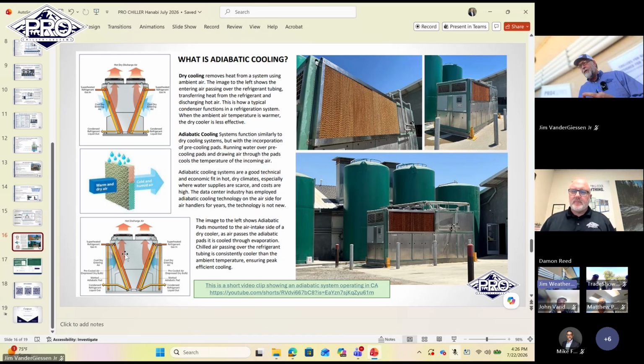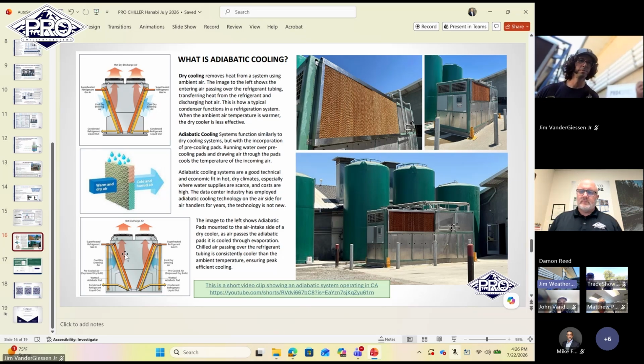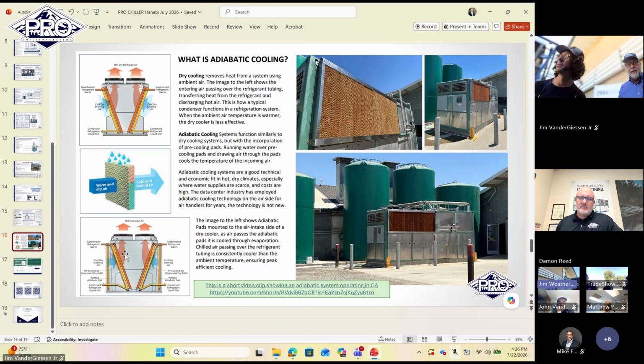Yeah, and we've found one thing today: we're going to install a cumulative flow meter. So going forward, we're going to have an independent device logging that water usage. And as Nick mentioned, we don't recirculate through our pads. It's one pass, and what you really want is nothing at the end. You want most of the moisture to be evaporated before it gets there.